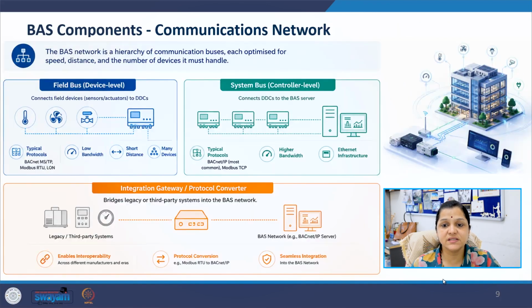In building automation components, the next point is the communication network, which is very important. It consists of several communication layers designed for different operational requirements. The field bus connects sensors and actuators with controllers. Common protocols include BACnet MS/TP, Modbus RTU, and LON. Field buses typically support many devices over short distances with relatively low bandwidth requirements. The system bus connects DDCs with the BAS server using BACnet IP and Modbus TCP. These are commonly used because they support higher bandwidth through Ethernet infrastructure.